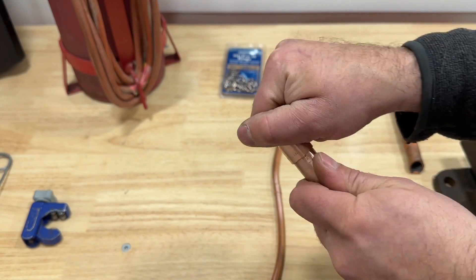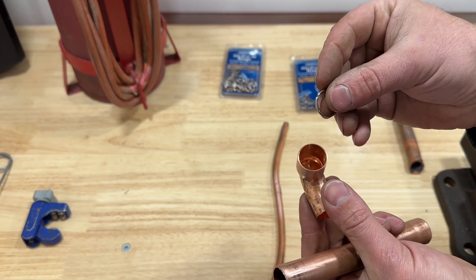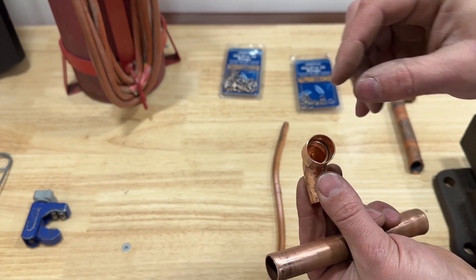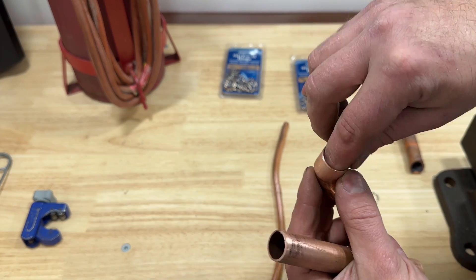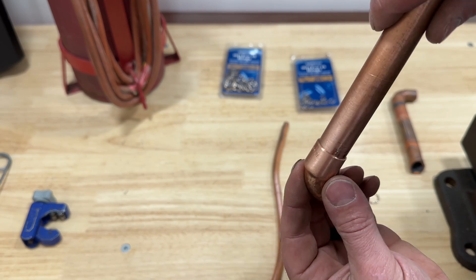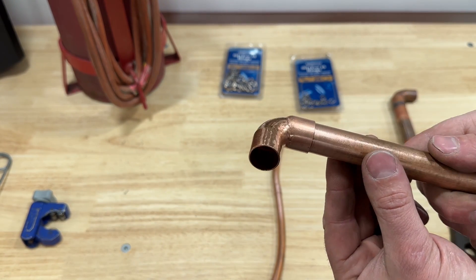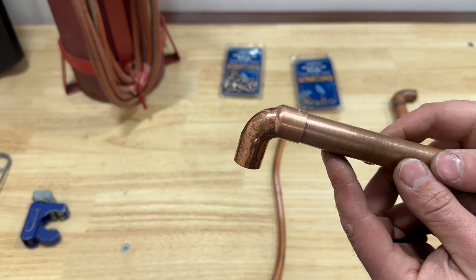Using these is extremely easy. All you do is take the right size ring, slide it down into the fitting, and push it all the way in. Then take your male end and feed it in until it's fully seated. And that's it — you are ready to braze this fitting.